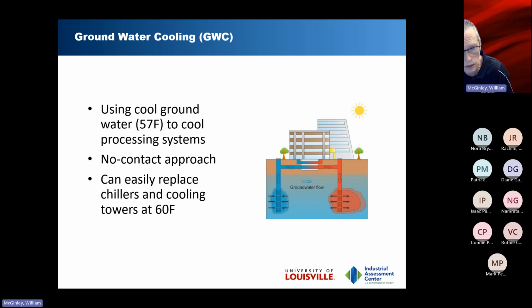So we're looking at groundwater cooling here because you've got 57-degree water down there, and there's a fair amount of it, not too far below the surface, with a nice 6-inch well. If you drill that down, you bring the water up through a heat exchanger and then dump it back down into the aquifer. You're not consuming that water, you're simply raising its temperature.